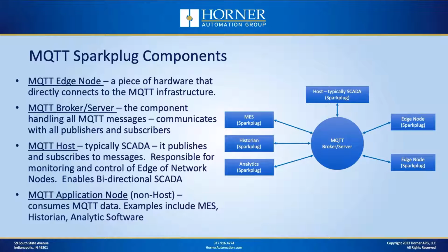So as an example, if you had the OCS reporting, let's say, a set point for temperature control, the SCADA, or the host, would be interested in seeing what the current set point is, but it also might be interested in changing that set point through SCADA and sending it back down through the communications route to the OCS. So with a host node with Sparkplug, that functionality can happen. You get the bi-directional capability we're all used to with protocols like Modbus TCP, for instance.